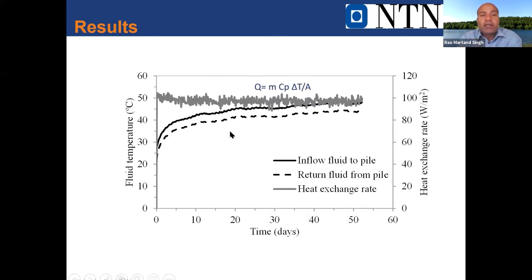This is the fluid temperature, showing inflow and outflow temperature. What we're interested in is this heat flux value shown here, which gives us about 100 watts per meter square. This can be used as a design thumb rule. If you have a number of piles and know the surface area, you can calculate how much energy you can get. So 100 watts per meter square is generally a good starting point when designing such a system.